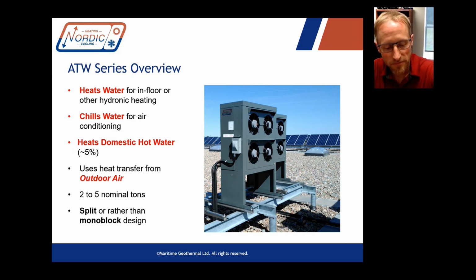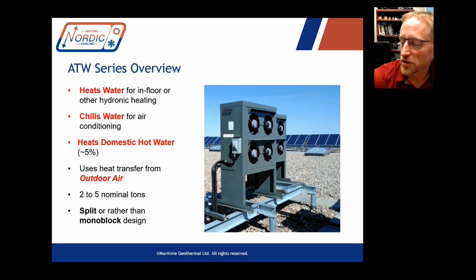Yeah, it's just like, Kara and I've had the debates or discussions about this, like where's the sweet spot of what capacity, what percentage of the peak load do you cover from your heat pump versus supplemental, right? Because obviously it's a bigger question with air source for sure. With geothermal, there's not too much reason not to try to cover the coldest day heat load with the heat pump. I know that 75% or 70% is a common number, but we recommend that people seem to be happier if their backup heat isn't running, kind of thing, when it doesn't have to be.